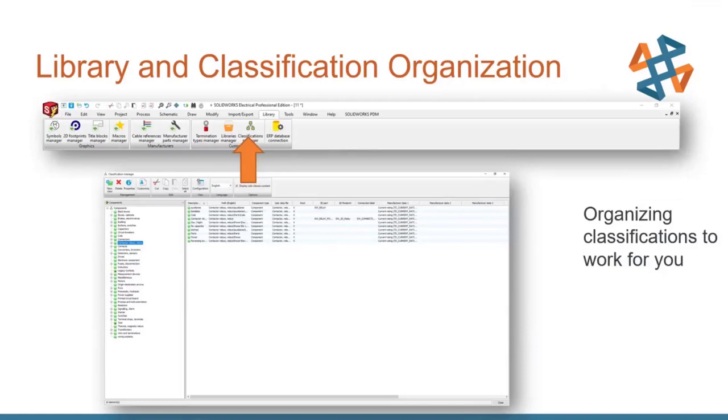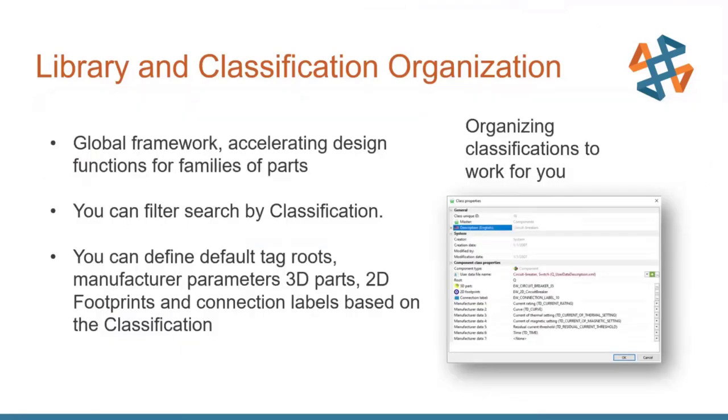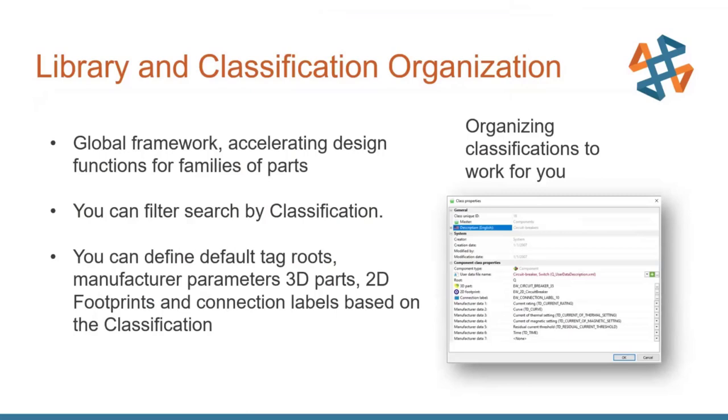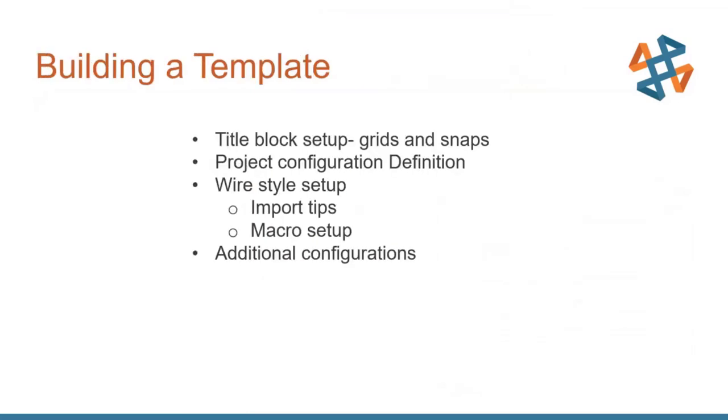The next is setting up classifications. Now a classification you can think of as the software doing some work for you. What work can be done in your classifications? And that classification can be set up in your classification manager. Essentially, think of this as the global framework. So this is going to do things like giving you roots for your symbols. So you drop in a motor symbol. That motor symbol is in a motor class. And anything in a motor class is going to give you the root M. You can also set up 3D parts and 2D footprints and so on that are broad sweeping. So maybe you have a bunch of panel manufacturer parts. And you want all your panels to reference the same footprint and to scale automatically for you when you use that. That can be handled very efficiently by just setting it up in your class.